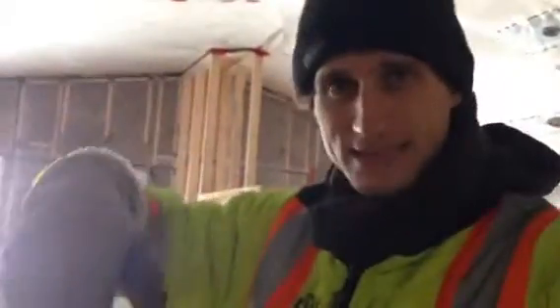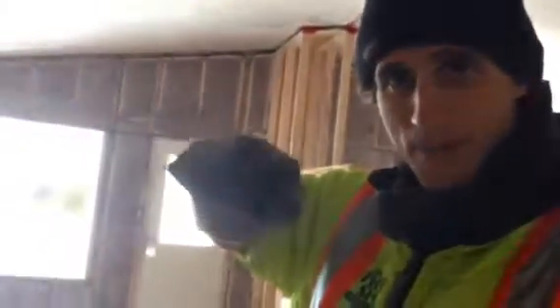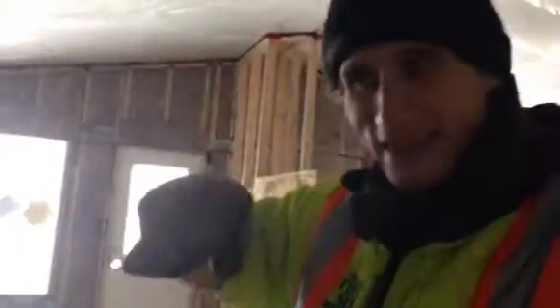And if you go into an attic in minus 40 degrees Celsius weather, you can find out where all your holes in your attic are. Every little wire that was missed when they were caulking, if they missed any. Every light box where the plastic on that plastic box that goes over top, if the end ends up curling up and lets air out just a little bit, you will have a frost plume that comes right off of that hole.